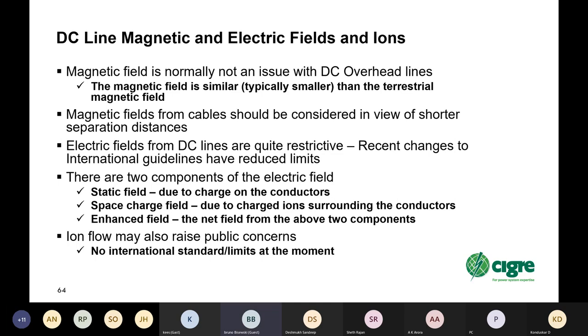There are two components of the electric field from the line: a static field and a space charge field, due to the charged ions that are released from the conductors, especially under inclement or wet weather conditions. The total field, or enhanced field, includes the net field from both the static field and the space charge field. Also, in some jurisdictions now, ion flow may raise public concern, but there are no international standards or limits at the moment on ion flow.